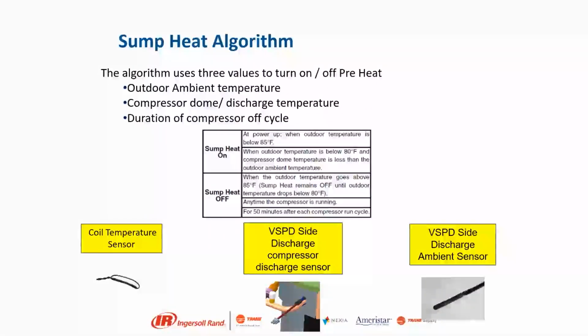If you've ever considered the crankcase heater on variable speeds, so your heat pumps, 14, 15, and 16 SEER heat pumps, you have to have crankcase heaters. And those crankcase sump pump heaters are connected right into the line voltage, so it's getting continual voltage. With the variable speeds, there's an algorithm that uses the value to turn off and on the preheat. So it's using the compressor windings along with the ambient sensor and the coil temperature sensor and the discharge sensor to detect if it needs to warm that compressor up.